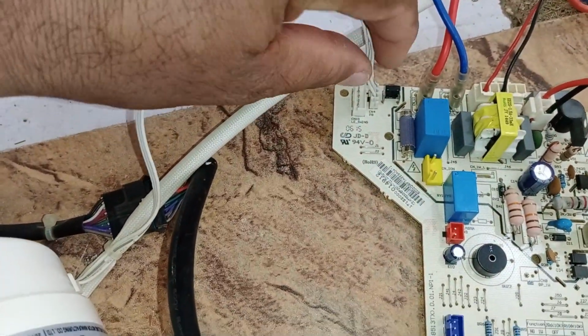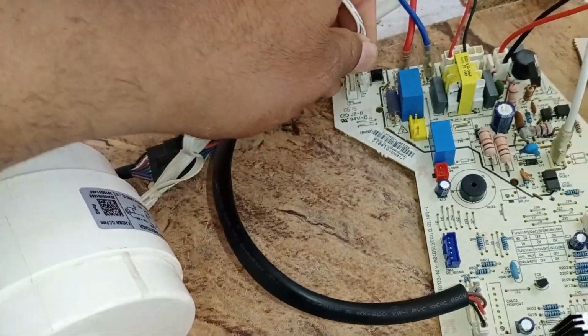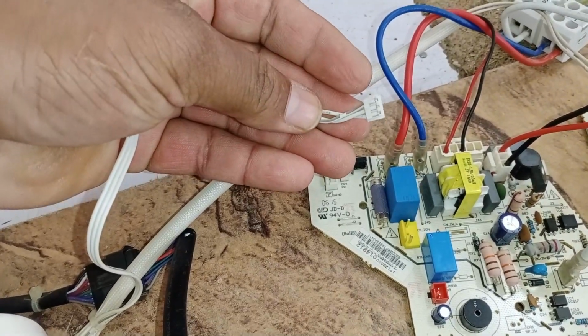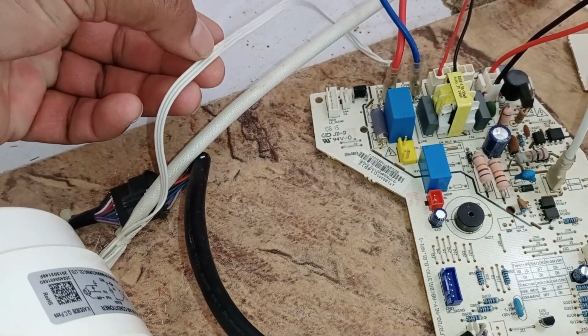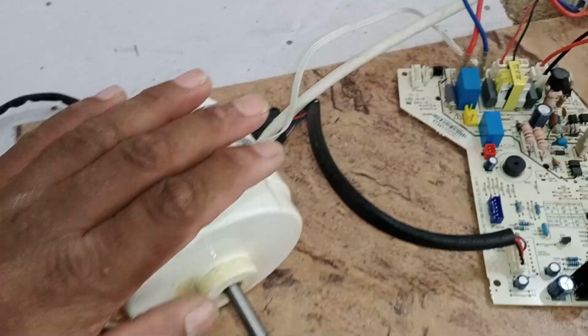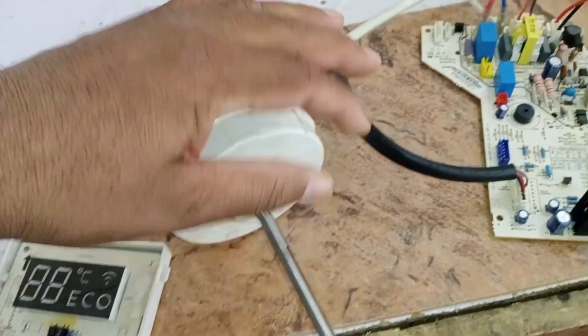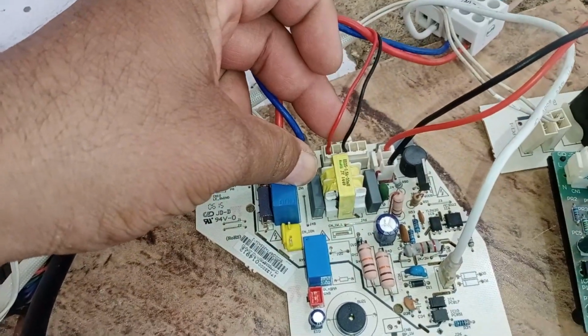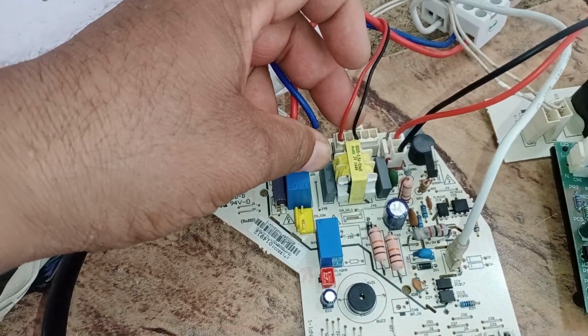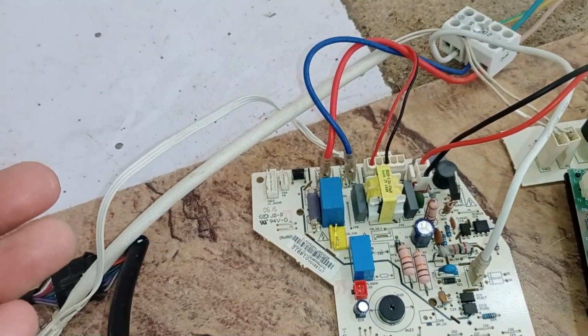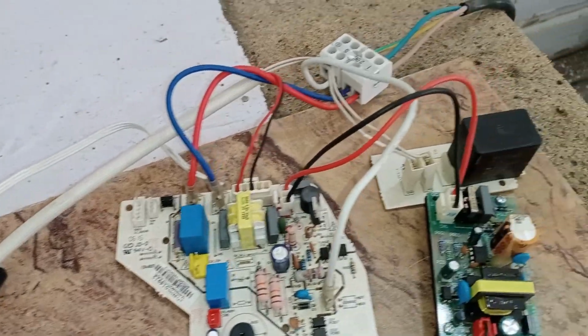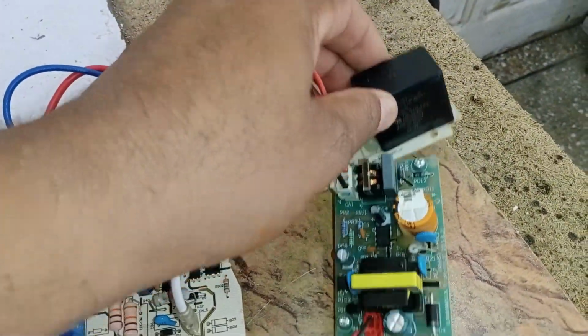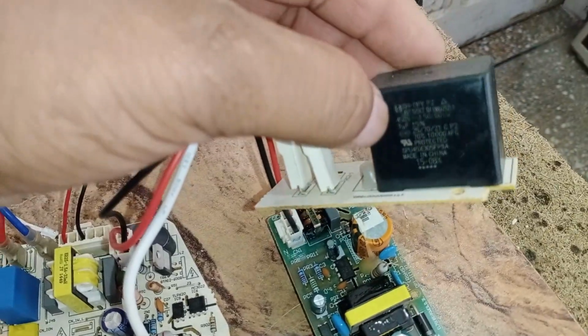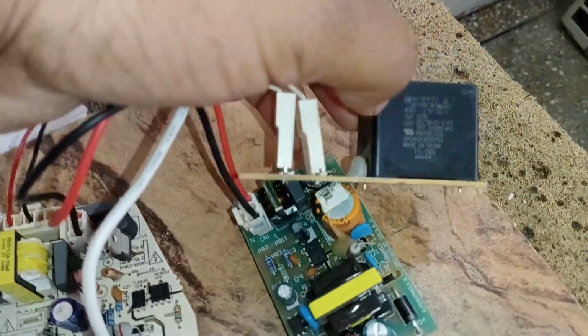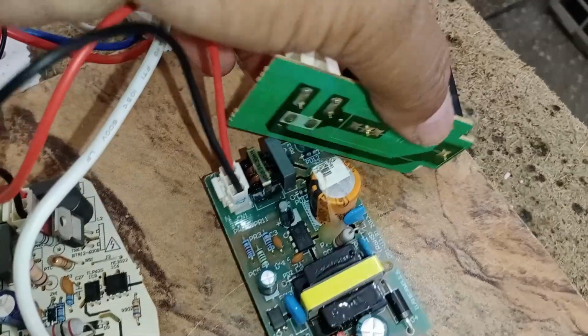Additionally, if the motor's wires are not properly connected or there's a loose connection, the E3 error will also appear. If a wire is cut or damaged, this will lead to the same issue. If the motor isn't running because it's not receiving electricity, you should check the motor's connector. If the wires from the connector are broken or cut, the motor won't receive power, and the error will persist. Moreover, there's a capacitor associated with the motor. If this capacitor becomes weak, it can also cause the issue. This is a 3 microfarad capacitor, and replacing it might resolve the problem and make the unit work properly.